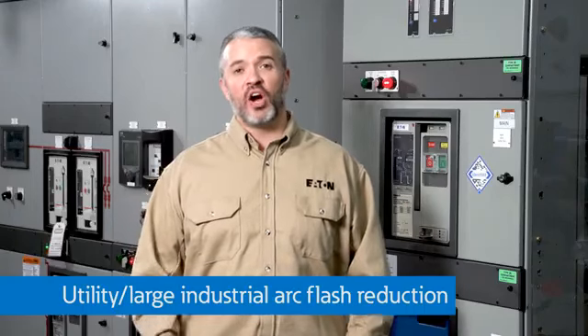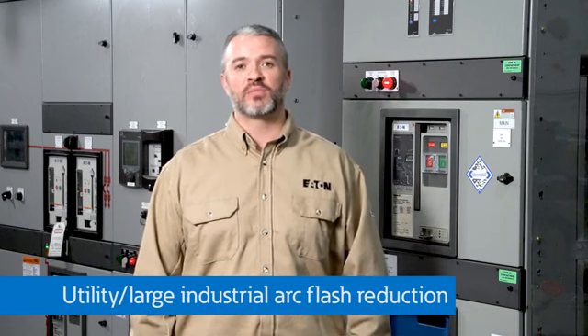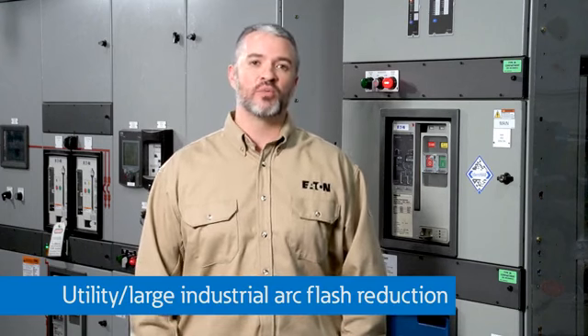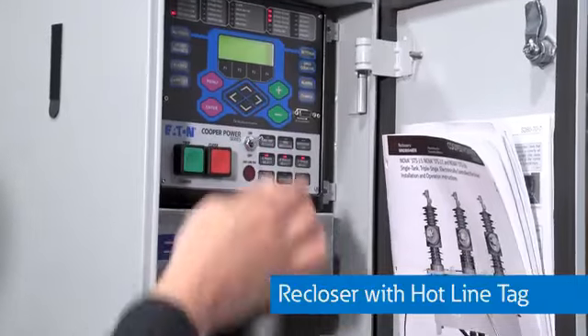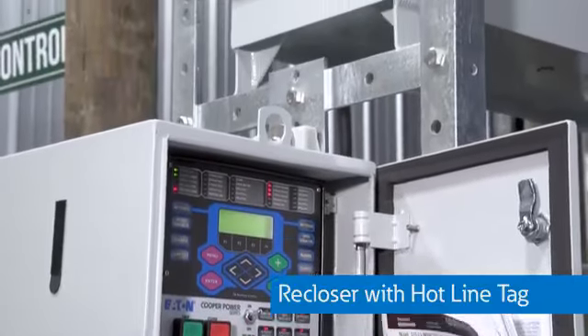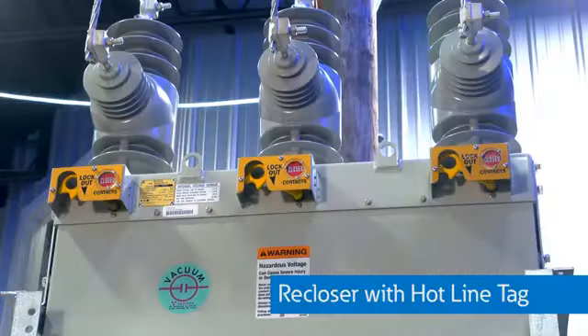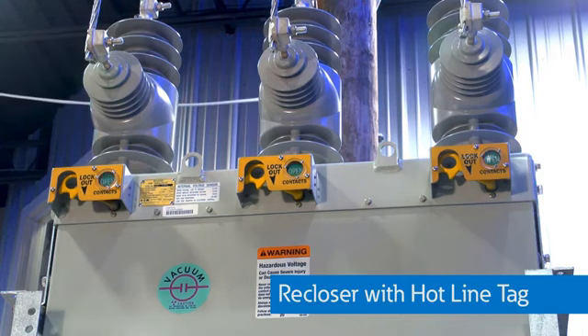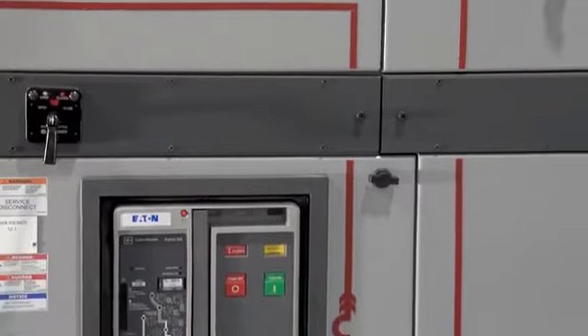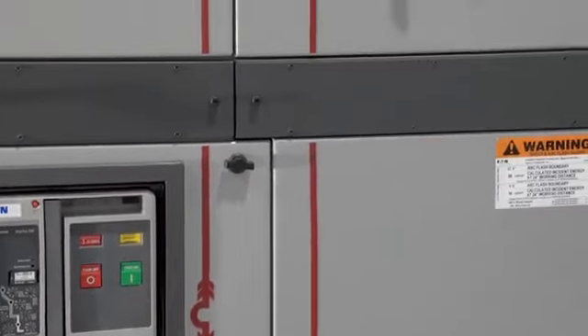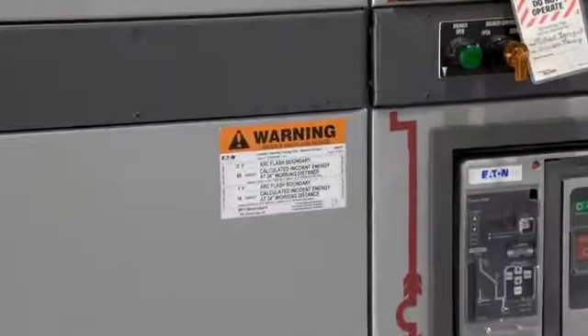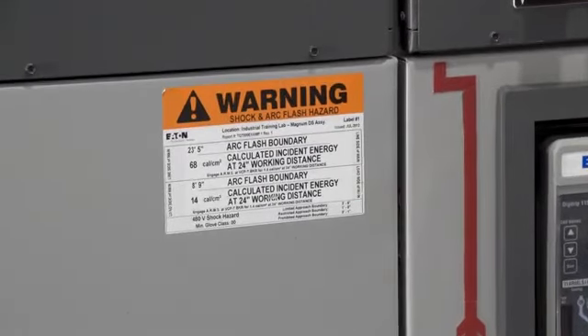With a lock applied at the breaker during your lockout tagout procedure, you can ensure that you are protected while working on downstream equipment. A variation of the ARM system for utility power systems or for large industrials that use vacuum reclosers like this one is the hotline tag, which essentially will lock the recloser, tripping as fast electrically as the device can mechanically, and locking out after one event. This can significantly reduce arc flash energy for medium voltage systems. For most power systems, the highest level of arc flash energy on low voltage switchgear is on the source or line side of the main circuit breaker.